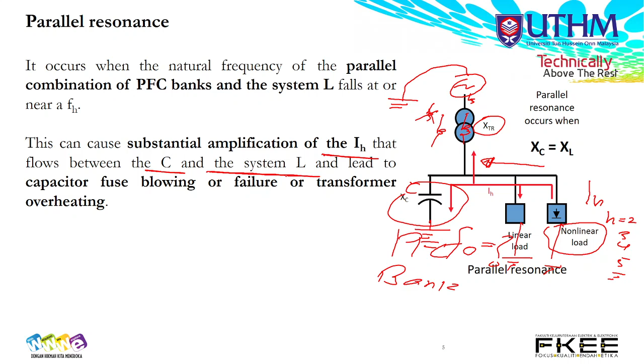This can cause substantial amplification of the IH, the harmonic current that flows between the capacitor and the system inductor, leading to capacitor fuse blowing or failure. So the effect is the capacitor can blow after a certain limit, or failure of the capacitor, or overheating of the transformer - that's the effect at a certain limit.